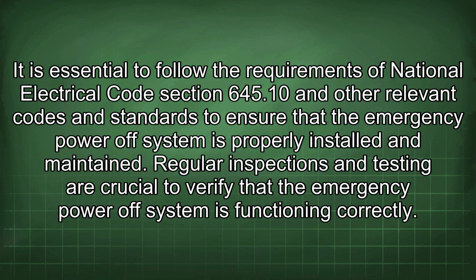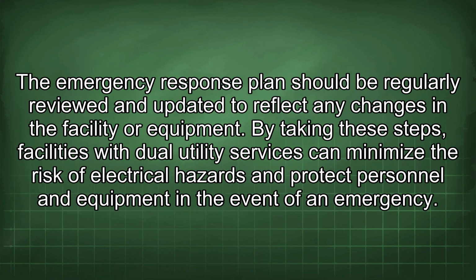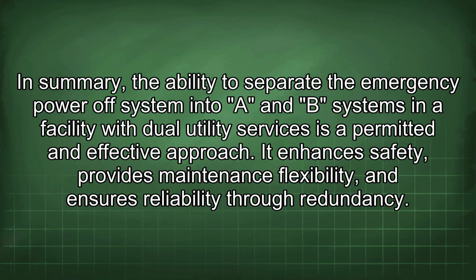Regular inspections and testing are crucial to verify that the emergency power-off system is functioning correctly. The emergency response plan should be regularly reviewed and updated to reflect any changes in the facility or equipment. By taking these steps, facilities with dual utility services can minimize the risk of electrical hazards and protect personnel and equipment in the event of an emergency. In summary, the ability to separate the emergency power-off system into A and B systems in a facility with dual utility services is a permitted and effective approach. It enhances safety, provides maintenance flexibility, and ensures reliability through redundancy.